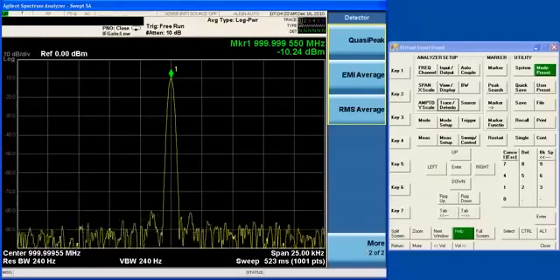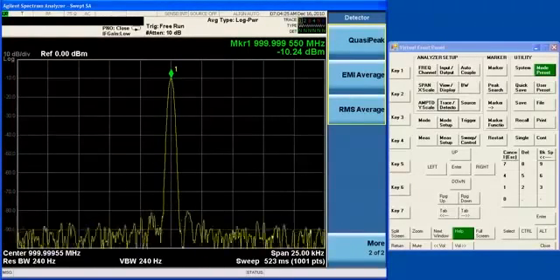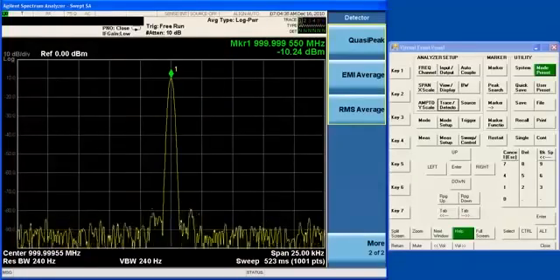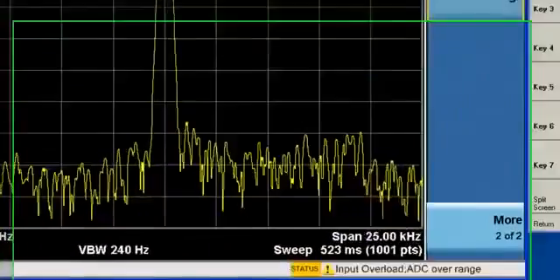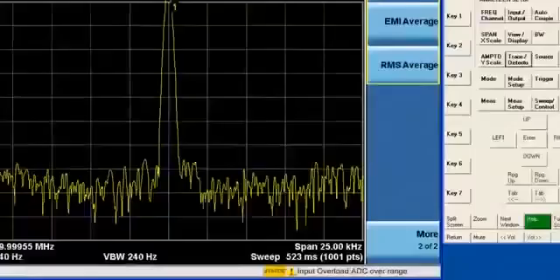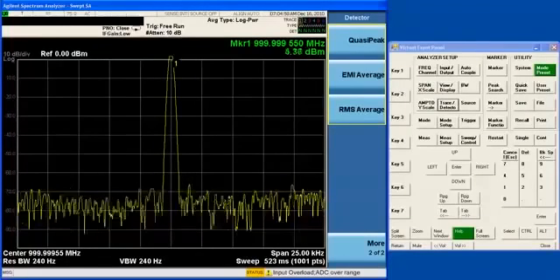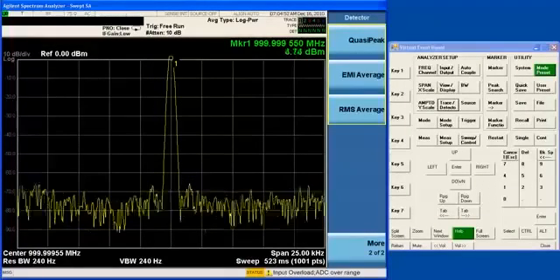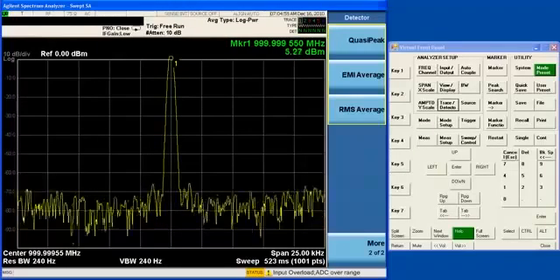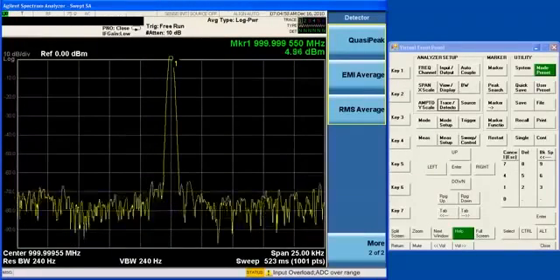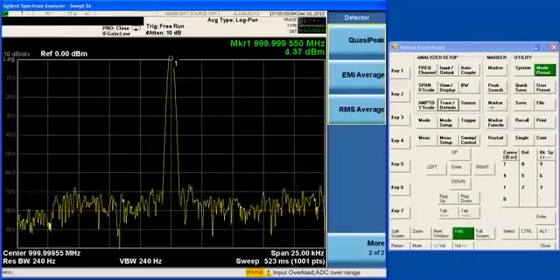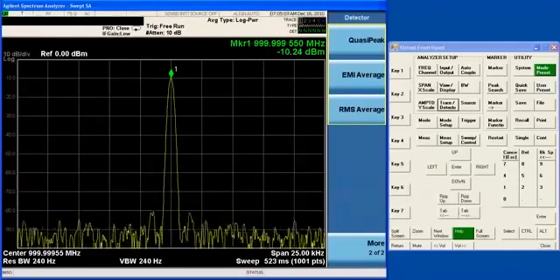Of course, the X-Series includes an overload detector. Any time the signal amplitude gets too high, the overload detector will go on, instantly telling you that you need to reduce your signal level. And this is absolutely crucial when you are making EMI measurements. If you get an overload, it is going to invalidate all your readings even at other frequencies. So, the overload detector is an essential part of the digital IF.